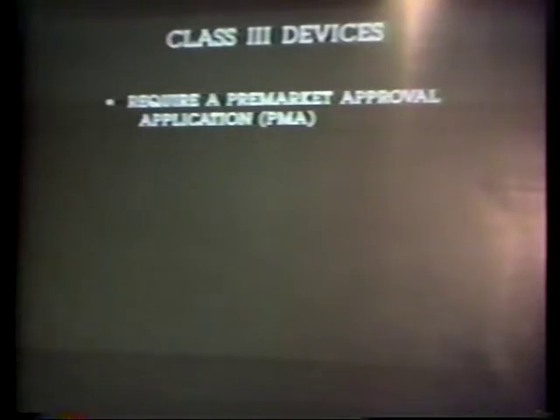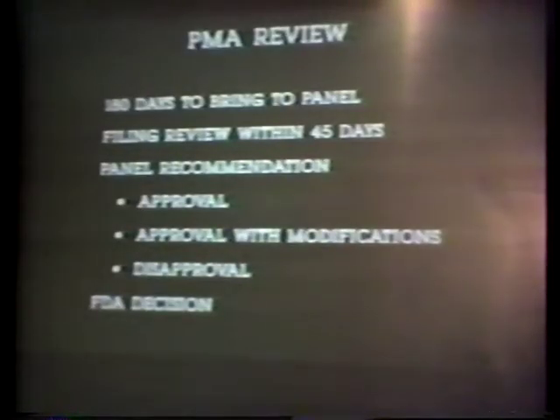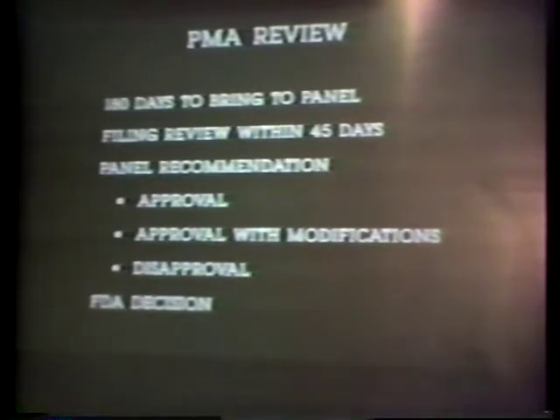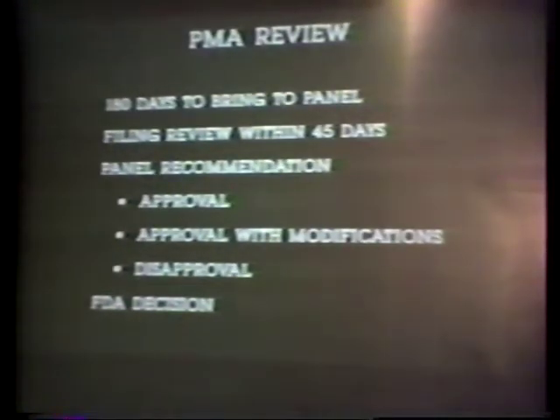In order to market a Class 3 device, an FDA-approved pre-market approval application, or PMA, is required. A PMA is a major submission that includes technical sections, preclinical and clinical sections. When the PMA is received by FDA, it is assigned to a team leader who puts together a team to review the document. A team is a group of individuals with different areas of expertise and includes a statistician, could include a toxicologist, clinician, chemist, biomechanical engineer, and may include reviewers from FDA's consultant base, which I'll mention in a few minutes.